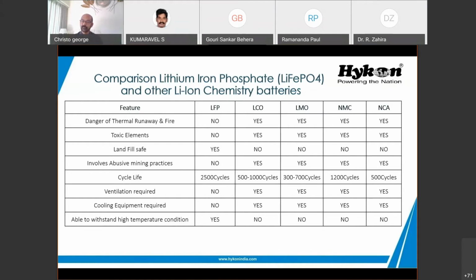So it is critical at 45 is the ambient temperature. Then when the battery is discharged at high current, another 10 to 15 degrees will build up. So we are talking about 60 or 65 degrees inside the battery cabinet. But that is the maximum range you can have for LFP. The range for other cells is very critical. You cannot withstand more than 40 degrees inside the battery. That's why in other European countries, NMC cells are more popular because the ambient temperature is much less than in India. In India, LFP is getting more popular because it can withstand high temperatures.